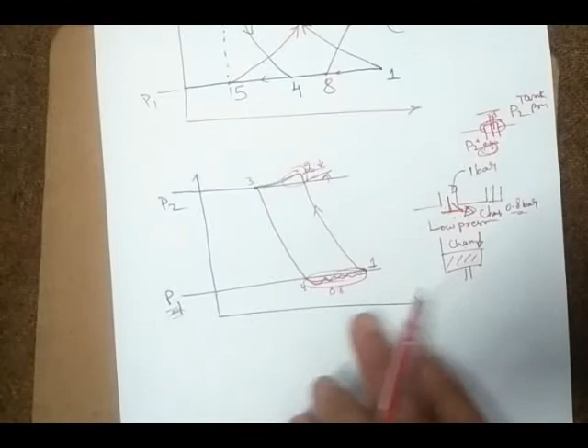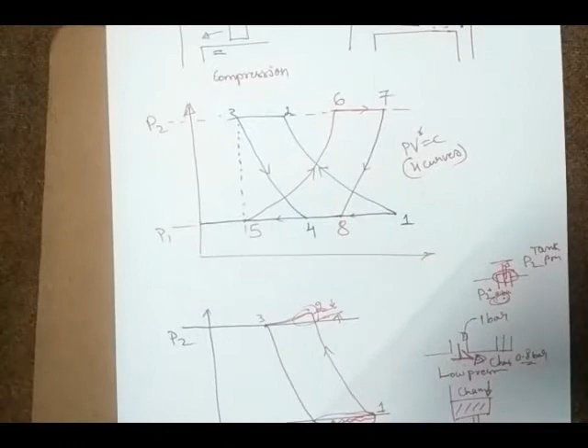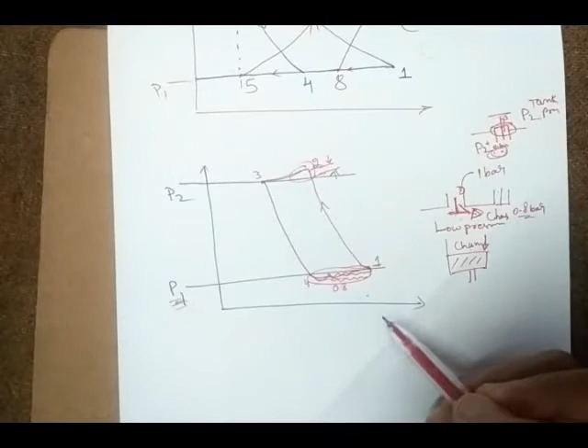So that means actual pressure is slightly different during valve operation. That's why this is the actual PV diagram. This is the ideal case, and this is the actual case. This is for single acting, and what I'm showing here is for double acting, because the single acting actual diagram I have already explained. Here there is a small wavy nature. This wavy nature is seen because the valve sometimes will bounce up and down, and that creates a wavy nature of the pressure curve during suction or during discharge.